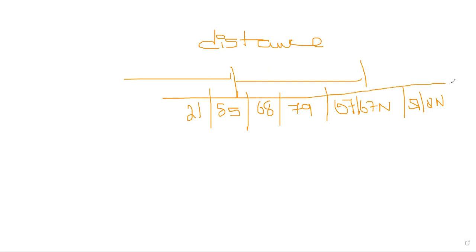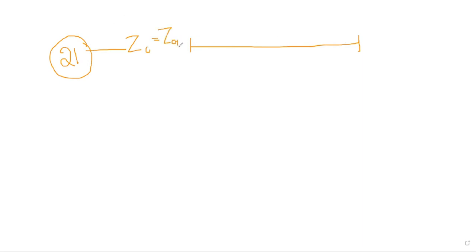So come to the line team. We have so many protections, and the main protection is the distance protection. What is the distance protection? Why is this distance protection required? The main important protection is the distance protection, which works on the principle of impedance of the line. If the calculated impedance and the apparent or applied impedance, meaning voltage with respect to the current, are both the same, then your protection will not operate. If it is more or less, then your protection will operate. This condition can be attained only for a single line.